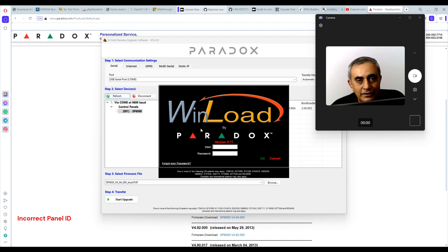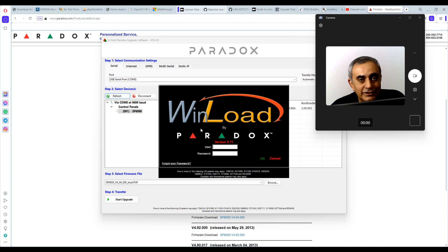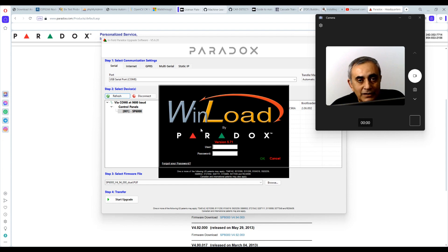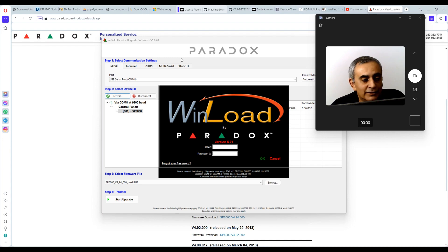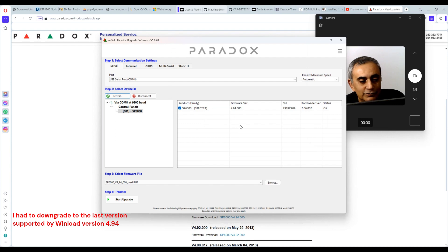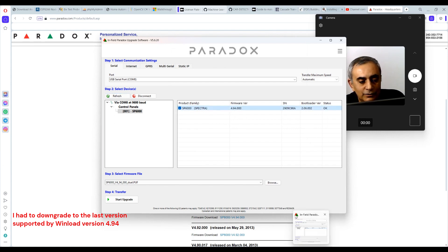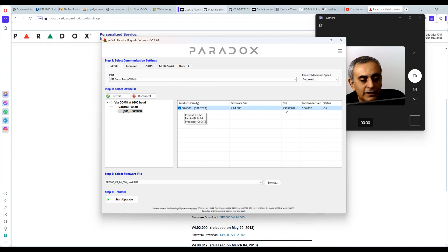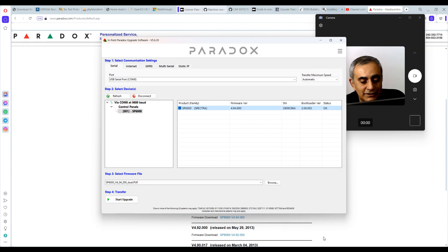It would say invalid panel ID and password. I tried everything. I verified with the keypad that I was using the correct panel ID and password and it still wouldn't let me in. So I had to get the latest infield software to downgrade it to the latest version supported by WinLoad, which is 4.94. So I had to downgrade and then I was able to log in. Let's go back to WinLoad.